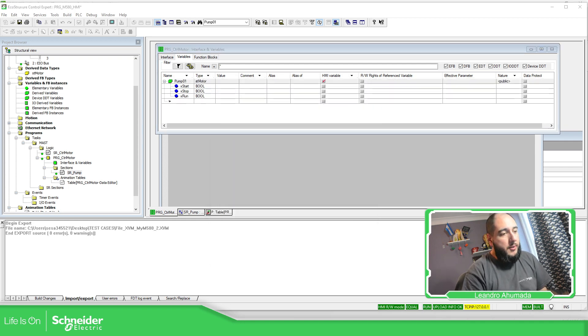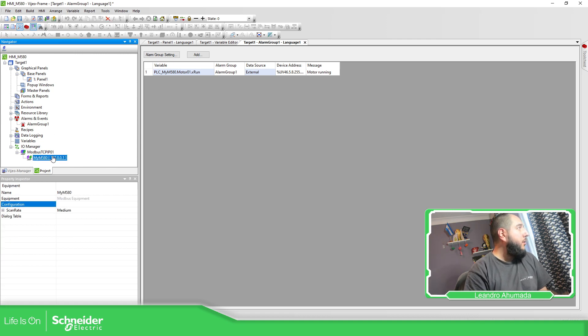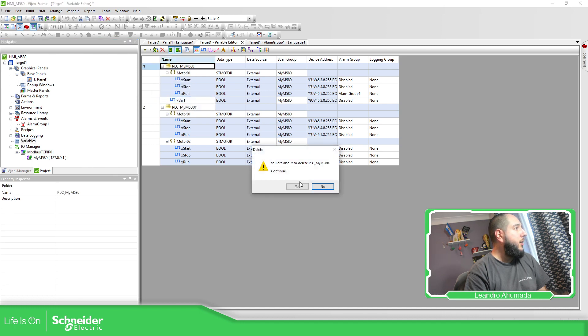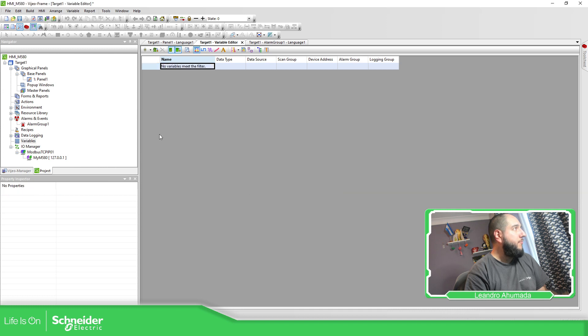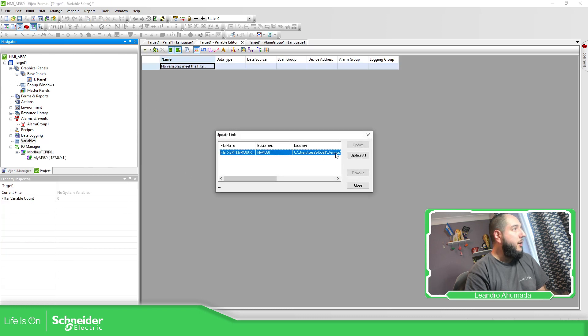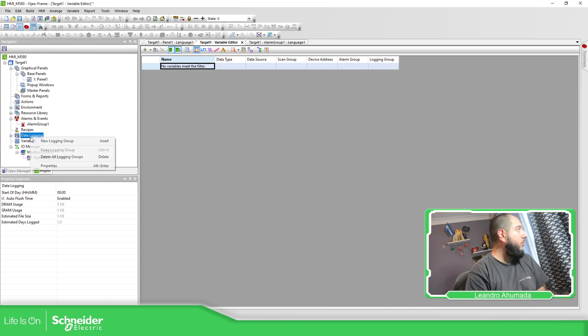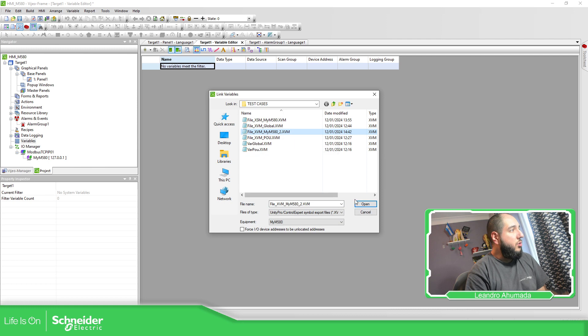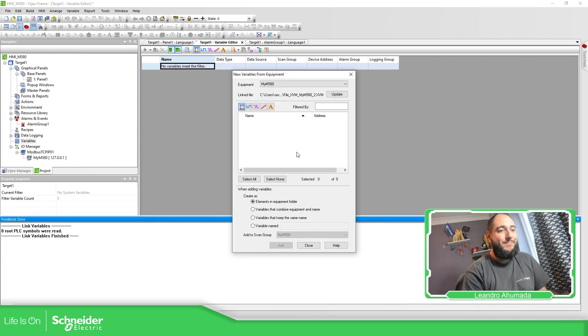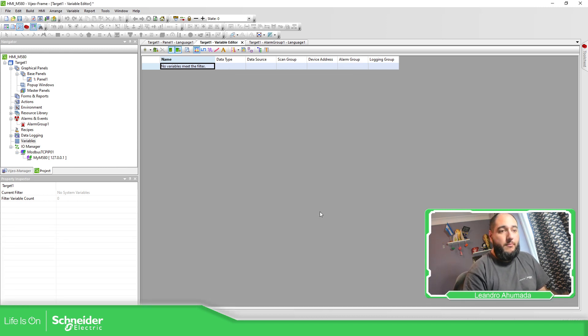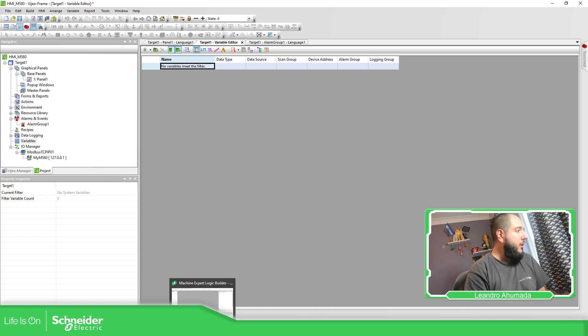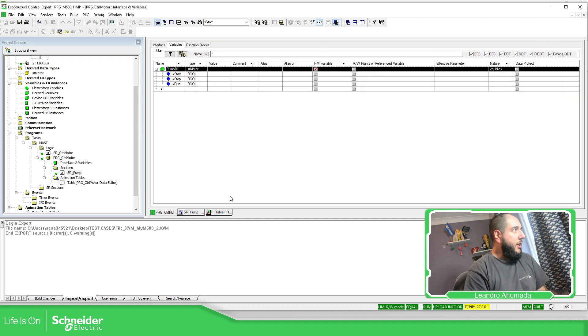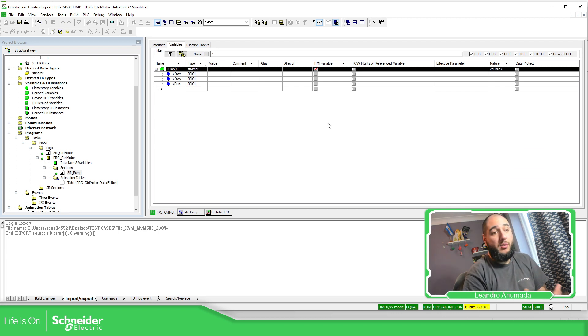So on Vijeo Designer, I'm going to delete the existing link, start from scratch, go to link variables, select the XVM file — m580 underscore 2 — and open it. There are no symbols at all. I believe this is correct, and this is my thinking: a program unit is like a function block. Even if it's used, it doesn't create any variable addresses — that's why there are no unlocated variables or addresses. There is nothing to communicate with the HMI.